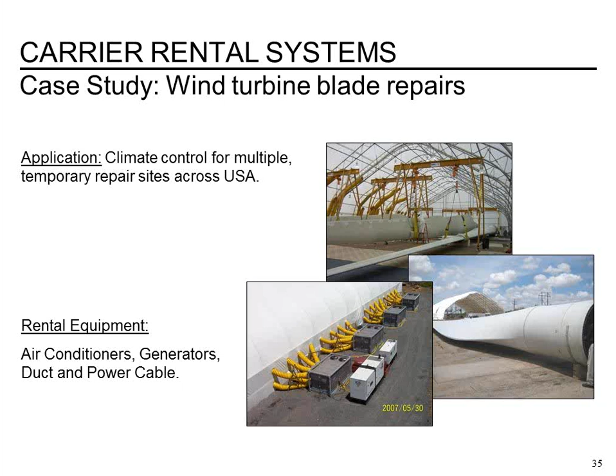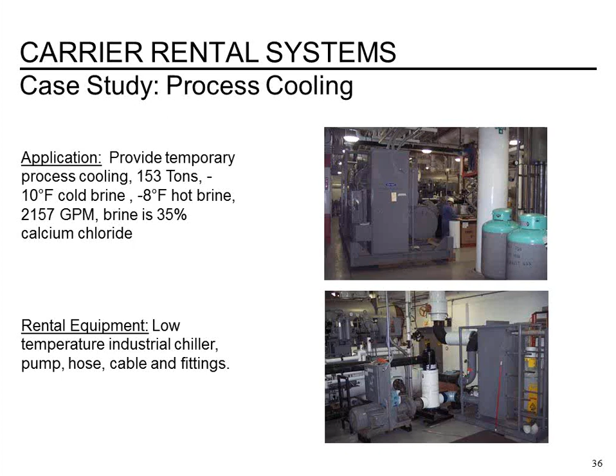Another application was at a food plant, actually a candy manufacturer. They had 3 systems. They had redundancy, and they still had a massive failure that brought the whole plant to a screeching halt. They were making a negative 10 degree fluid, coming back at negative 8, and this went to many different parts of their process, cooling tunnels, that they had the candy going down to a drum that was turning, and the gooey center of the candy would pass over about a quarter of the drum and then be scraped off and go into the tunnel. Just the diverse applications we can get involved with. This was calcium chloride.